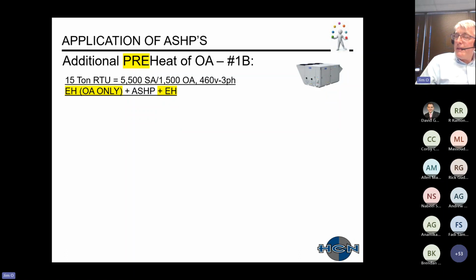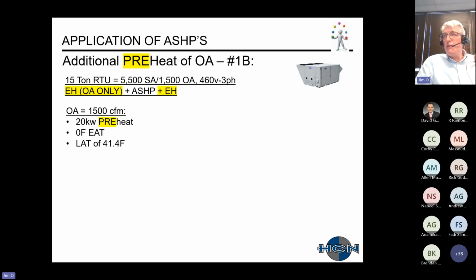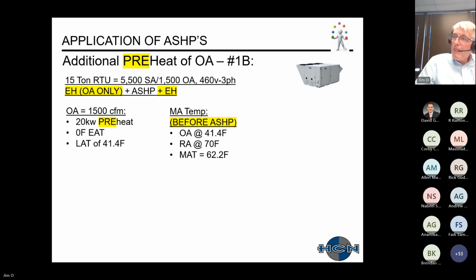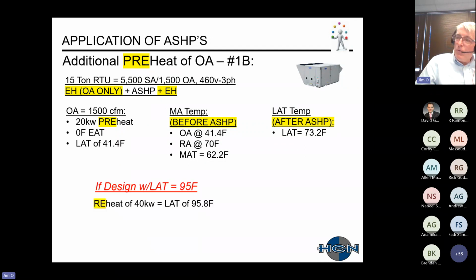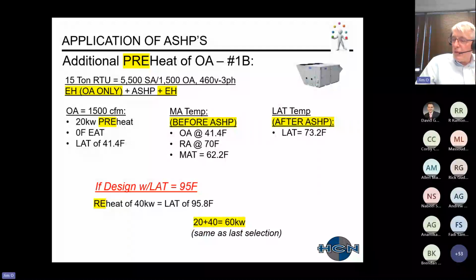All right. Other option, just quick: if we take a preheat of the outside air with electric as a preheat, this is only for the outside air. So this example here, just using a 20 kW heater to heat the air from 0 up to 41. Next, with our mixed air temperature before our air source heat pump, we get a mixed air temperature of 62.2, leaving air temperature of 73.2. So if we wanted a leaving air temperature of 95, we could put in a 40 kW heater to get our leaving air temperature. And then once again, just want to point out that, hey, 20 plus 40 equals 60. This was the same kW as the last selection.